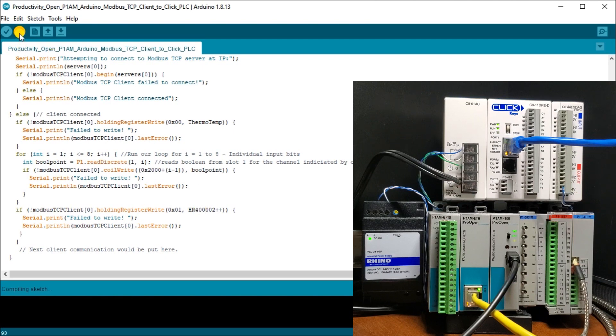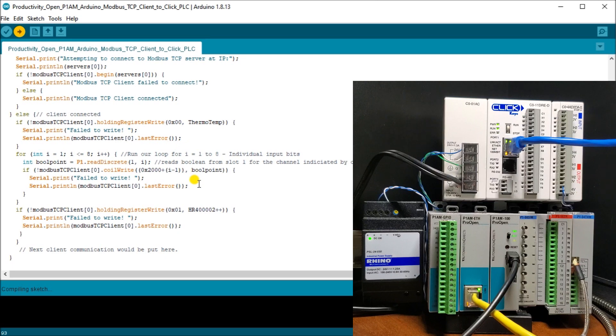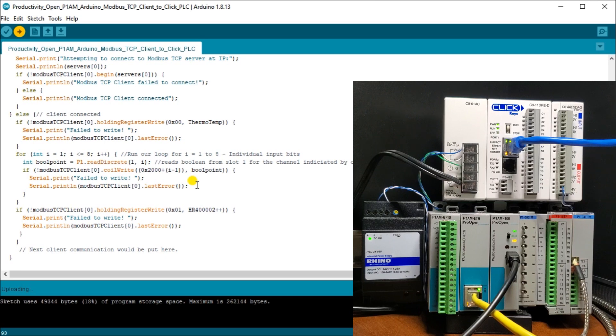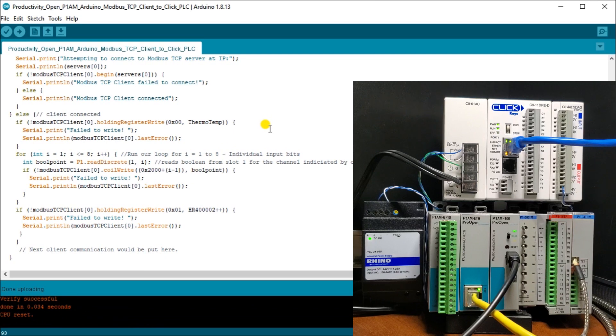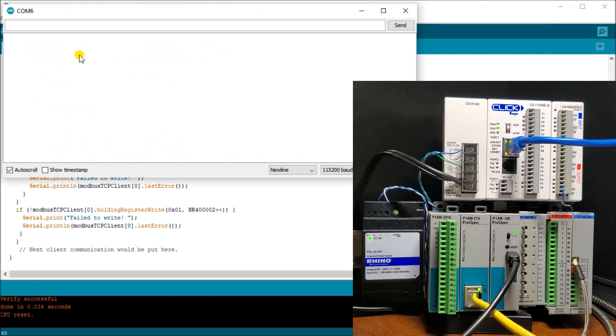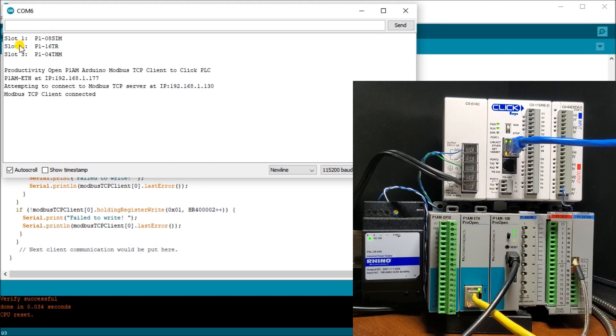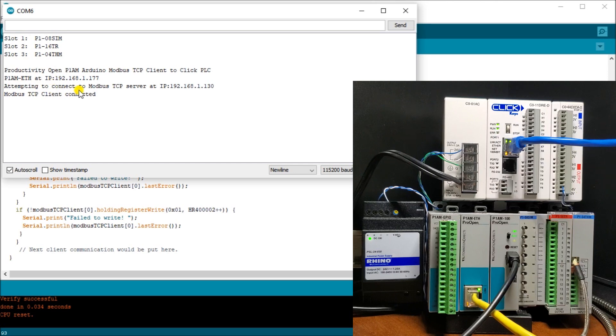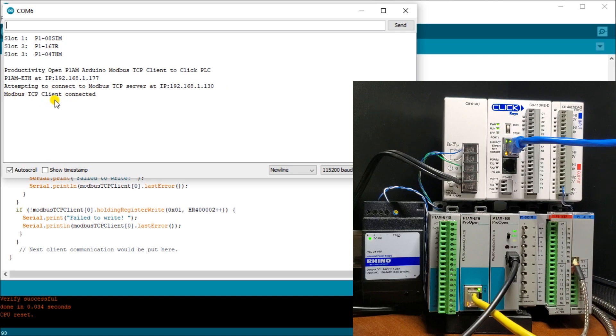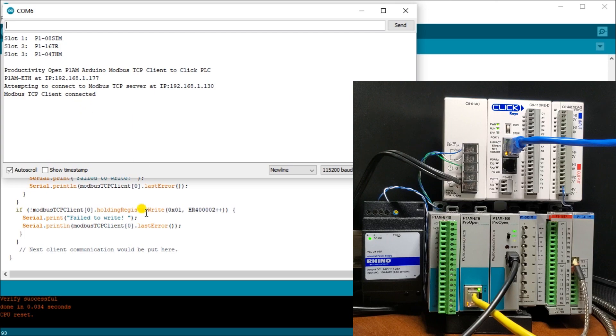What we'll do is we upload this now to the controller and once it's uploaded, just takes a couple of seconds here. It actually allows it to compile first and then it will upload. There we go. So everything's now uploaded to our controller and we will turn on our serial monitor and what we should see is it connecting. There we go. So it tells us what our cards are, where they are. Now it says that our Ethernet card is at that address, which is correct. Now it's attempting to connect to our server, which is our slave on our Modbus, which is our Click PLC, which is telling us right here. It's connected to it. And it's just telling us that our Modbus TCP client connected to our server or our slave. So everything looks like it's running fine.